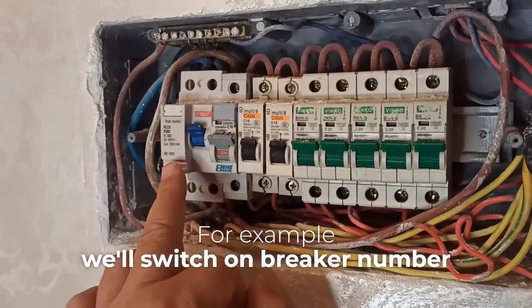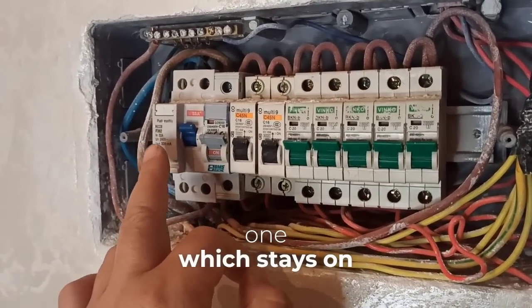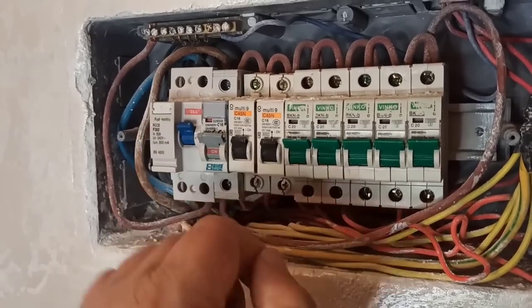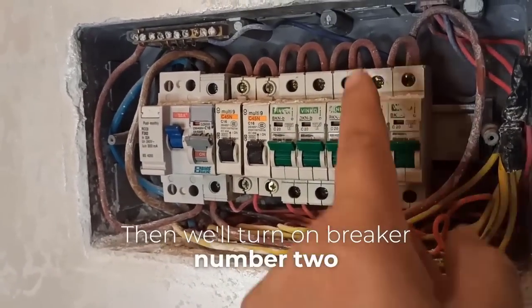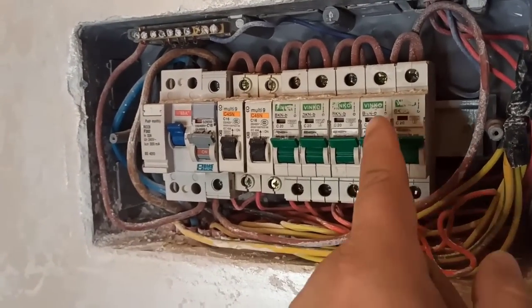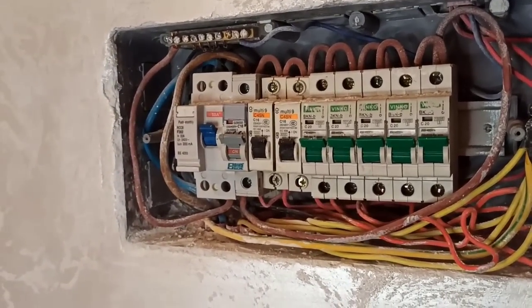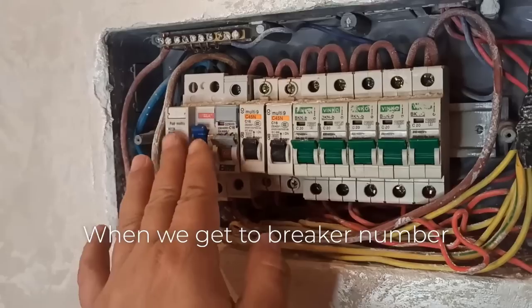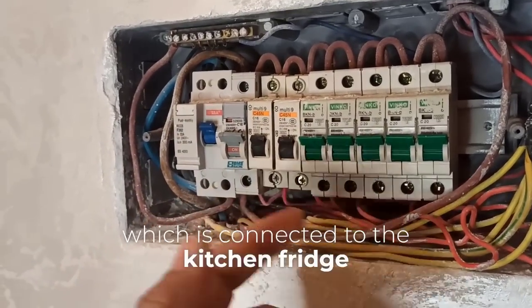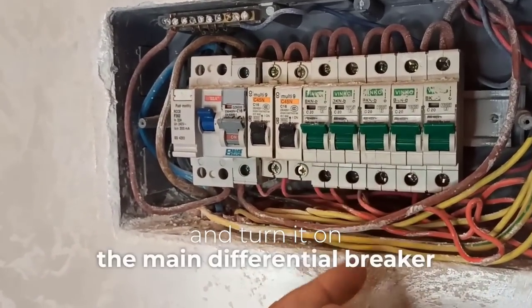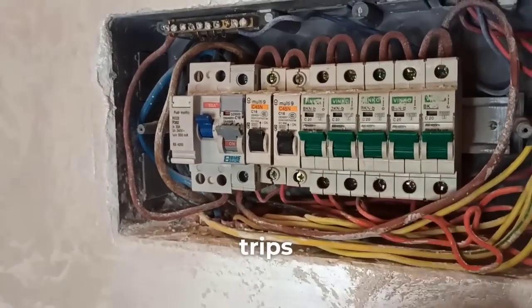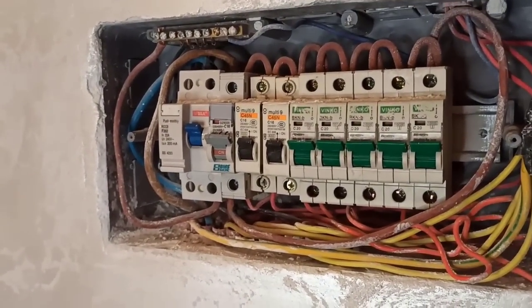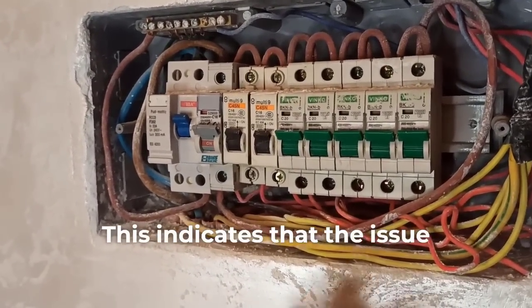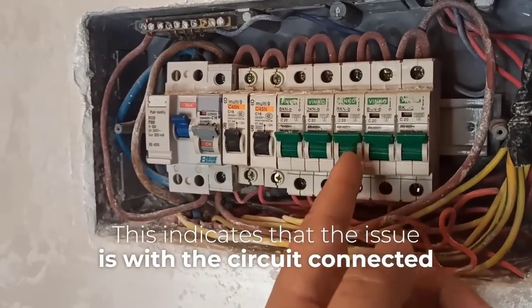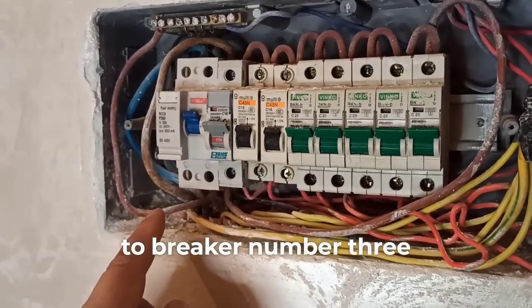For example, we'll switch on breaker number 1, which stays on. Then we'll turn on breaker number 2, which also remains on. When we get to breaker number 3, which is connected to the kitchen fridge, and turn it on, the main differential breaker trips. This indicates that the issue is with the circuit connected to breaker number 3.